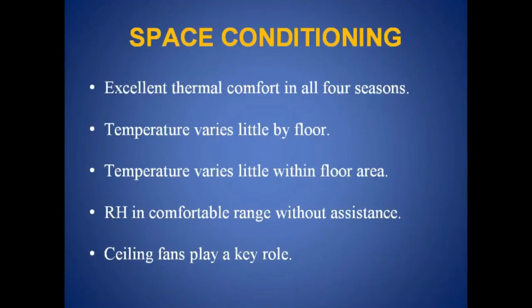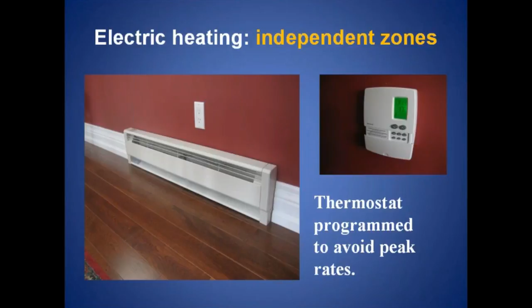This is the main heating system of the building - there are 3 zones of baseboard heaters. I would do this differently now, and have done it differently, but at the time I was trying to keep the system as simple as possible. Electricity is an expensive way to heat if you use a lot of it, but if you're not going to use a lot, it's actually not that expensive, and it's a very easy system to put in. That baseboard heater has no moving parts - unless I really take the dining room chair to it, it should last a really long time. It's connected to a thermostat which makes sure it mostly comes on during off-peak hours, so it can be programmed that way.